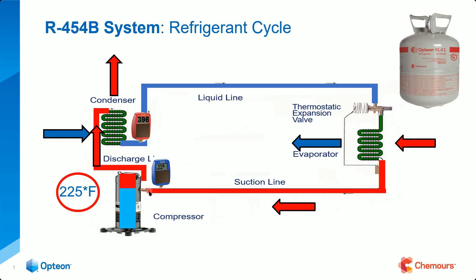The number one reason for overheat is high compression ratio — which basically means you either have high head pressure, low suction pressure, or the combination of both. We'll get into that topic on another day. But we're coming through here rejecting heat — and we're rejecting a lot of it: the heat from the load, the superheat, the heat from the motor, and the heat of compression.